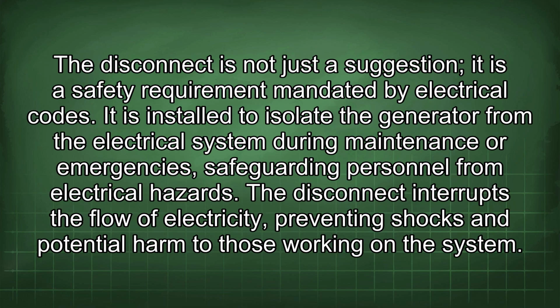The disconnect is not just a suggestion, it is a safety requirement mandated by electrical codes. It is installed to isolate the generator from the electrical system during maintenance or emergencies, safeguarding personnel from electrical hazards. The disconnect interrupts the flow of electricity, preventing shocks and potential harm to those working on the system.